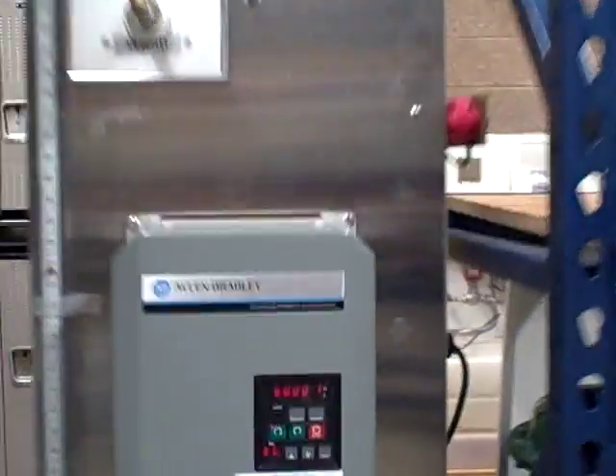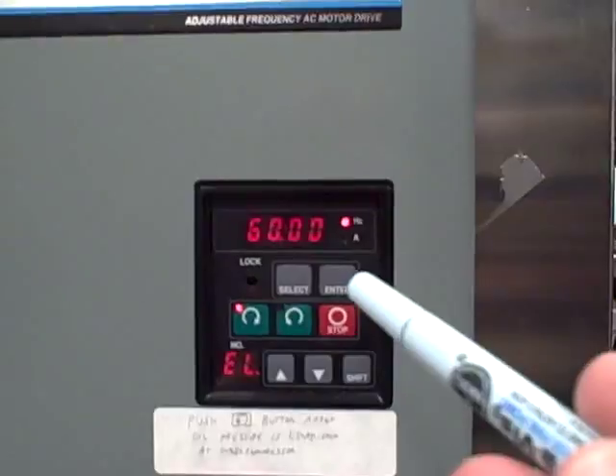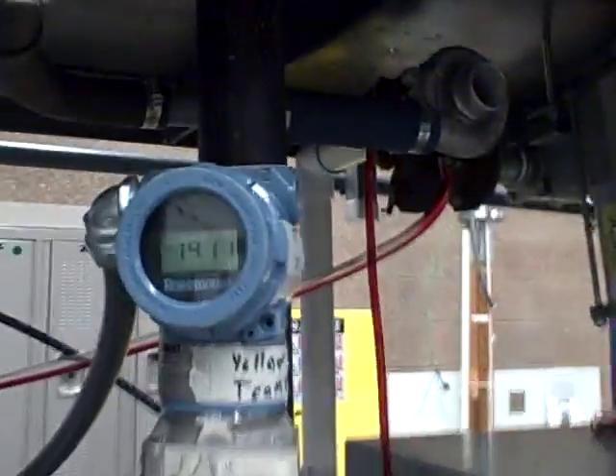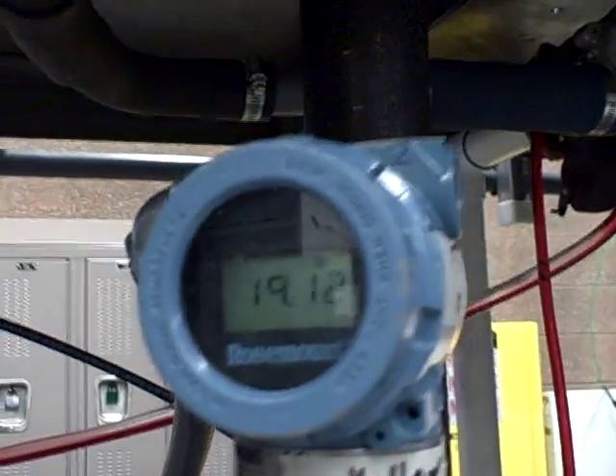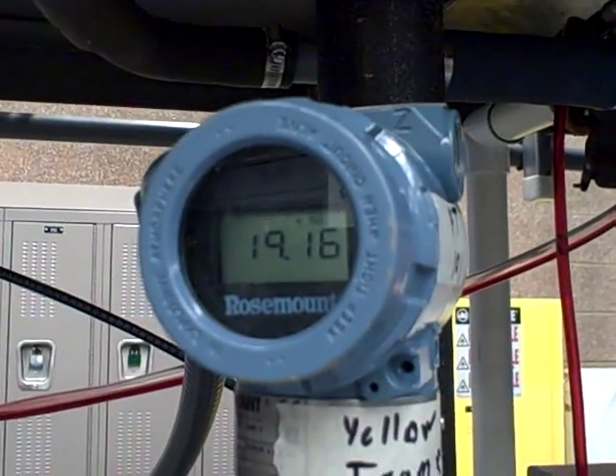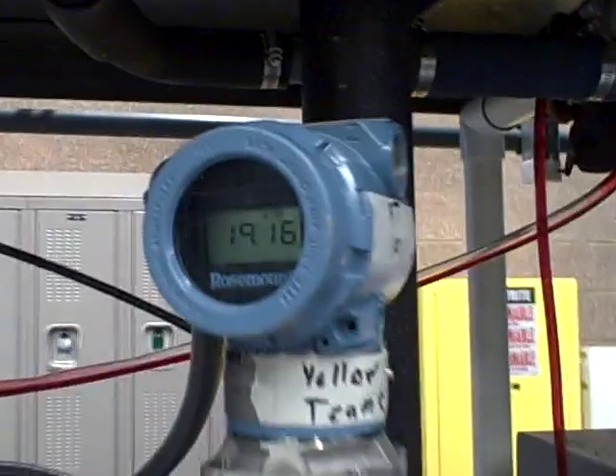The speed is 60 hertz, and the differential pressure we measure right here is 19.12, 19.16, close to the 19.3 inches of water column measured earlier.